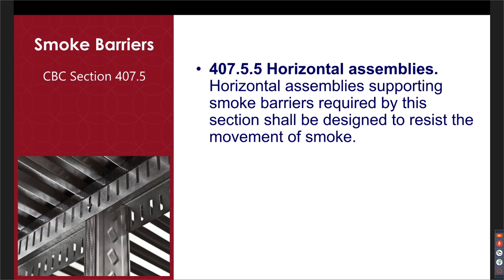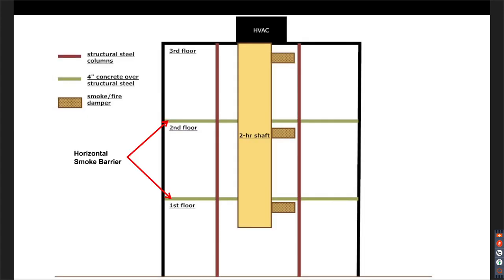Again, the horizontal assemblies that support those smoke barriers are also part of that smoke compartment. They have to resist the movement of smoke. So just a reminder that the floors, Nancy mentioned earlier, you're building a cube. So the floor below, the floor above, and all four walls are smoke barriers. In this case, the floors are horizontal smoke barriers, and that's significant because penetrations through those floors are required to be leakage or L-rated assemblies.